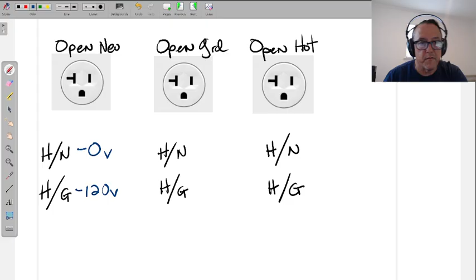Not so fast. Check that hot to ground as well. Because now, if you check the hot to ground and there is 120, then it actually means the hot is here, but the neutral's not here. And that's a different problem. The hot not there, that's a problem in one direction.